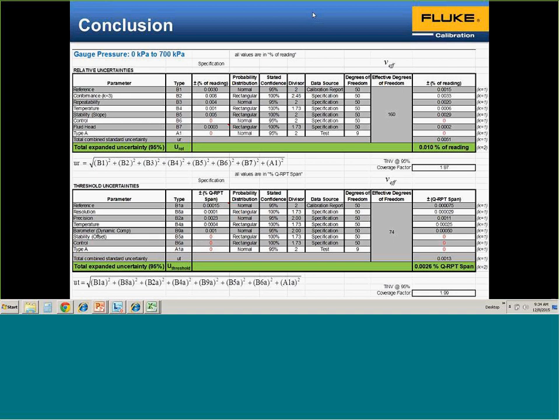It's significant at higher pressures, as a percent of reading. Usually for gas, it's about 3 ppm per inch. So if you're at 0, it really doesn't apply. But as you go up in pressure and the density of the gas increases, it's more significant. But if you say in your procedure, make sure your DUT is always brought up to the reference level of my controller, you really don't consider that. The final answer is that we consider everything, but if you find it to be at an insignificant point, you can state your head height as plus or minus an inch or centimeters. The additional uncertainty is 3 parts per million, and if you're doing 100 parts per million work, then 3 parts per million becomes very insignificant.